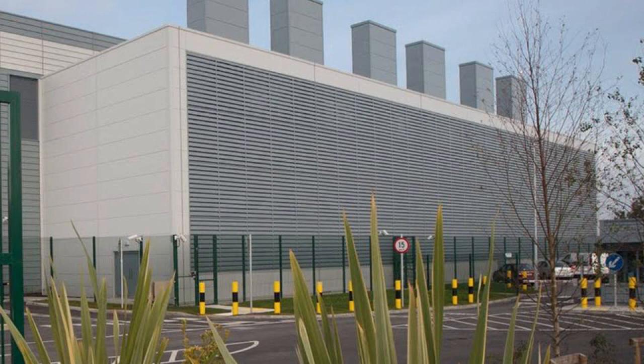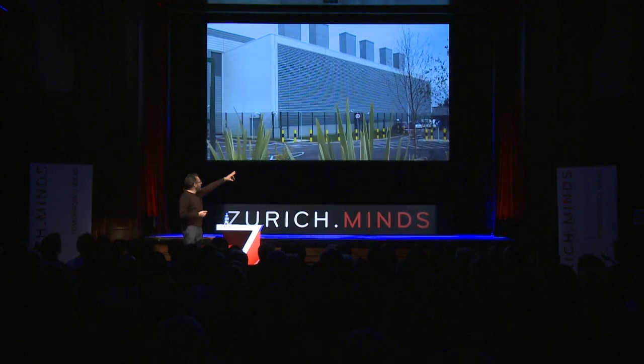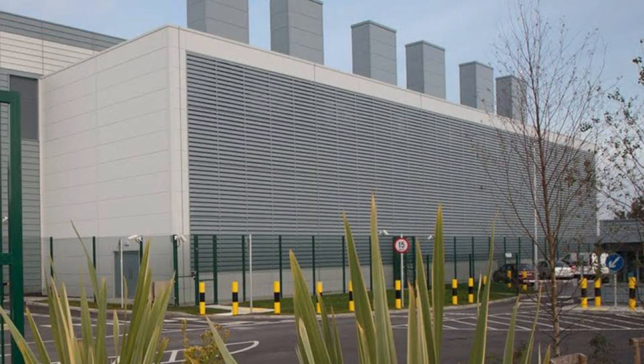This is a data center in Ireland. In that data center, because Ireland has perfect weather, at least if you're a data center guy, what I mean by that is basically never warmer than 27 degrees Celsius, just the outside air. So what we do here, this is basically a huge open wall with fans behind it, and it just pushes the air through the building out on the other side, and then replaces it with new air from the outside. So this is another way how you can cool things.